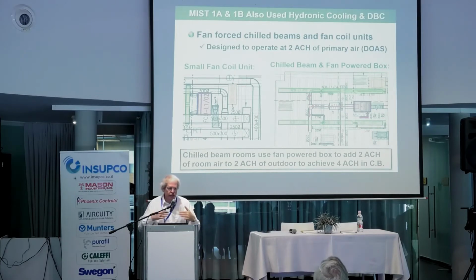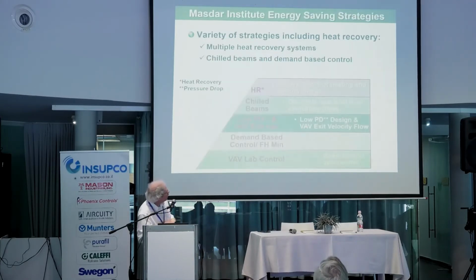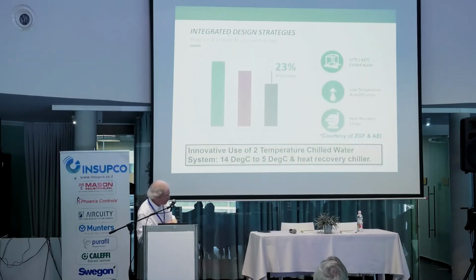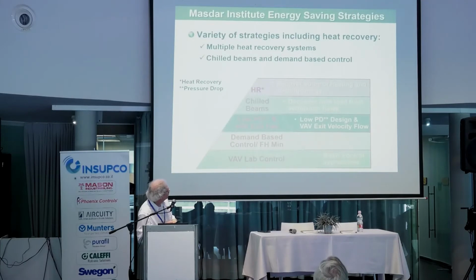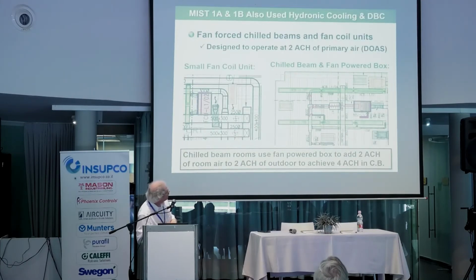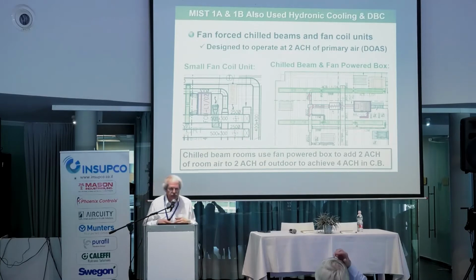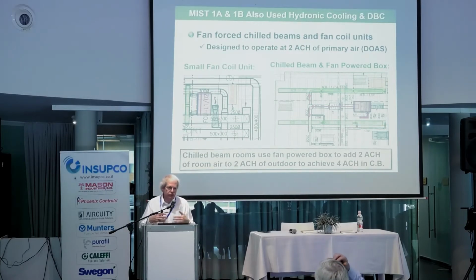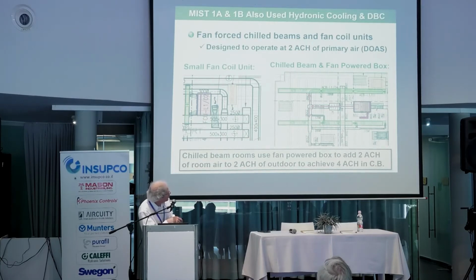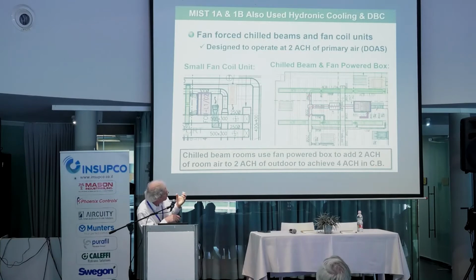They were actually using 2 air changes. The chill beams typically in this environment would actually need about 4 air changes to operate, just in terms of the way they work. They didn't want to use that much airflow, so they're using a fan-powered box. So they're bringing 2 air changes of outside air, and then they're using 2 air changes of air in the lab, and that's then going through the chill beams. So the beams are actually getting 4 air changes worth of airflow, but only 2 of that is coming from outside. So again, just using that air from inside.